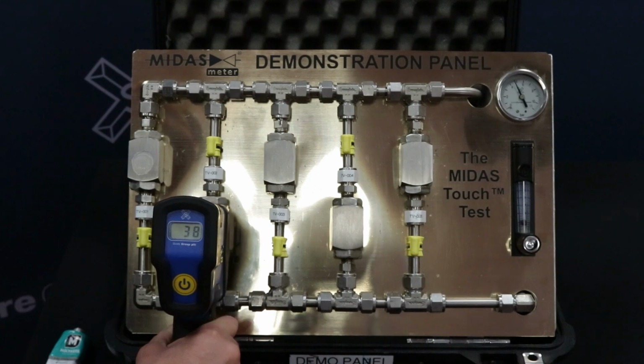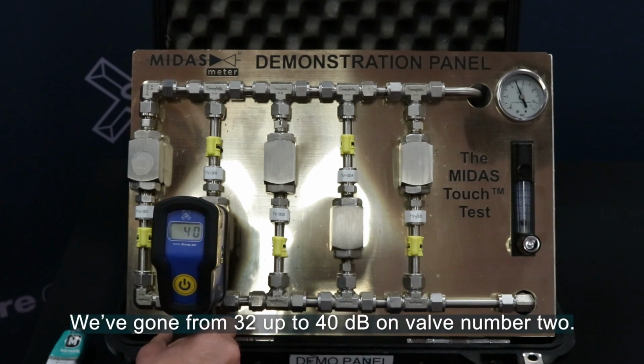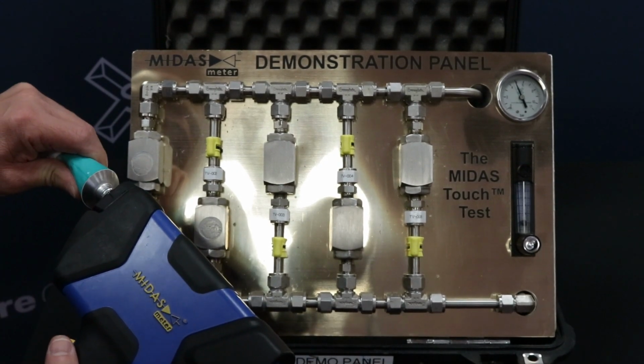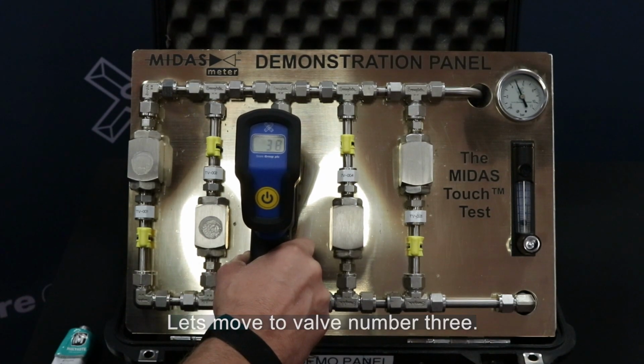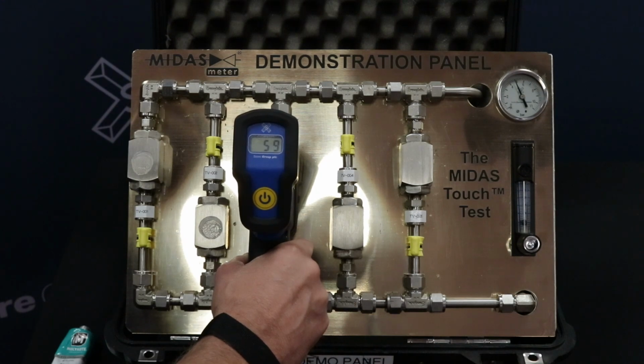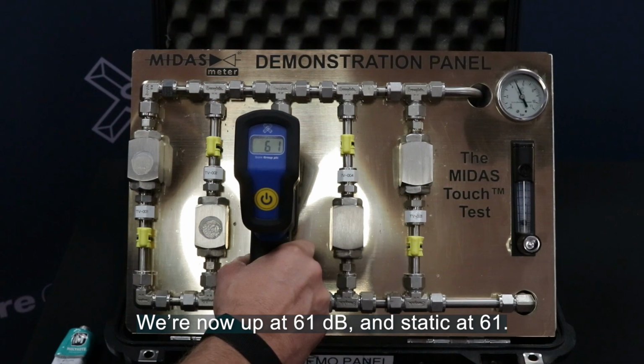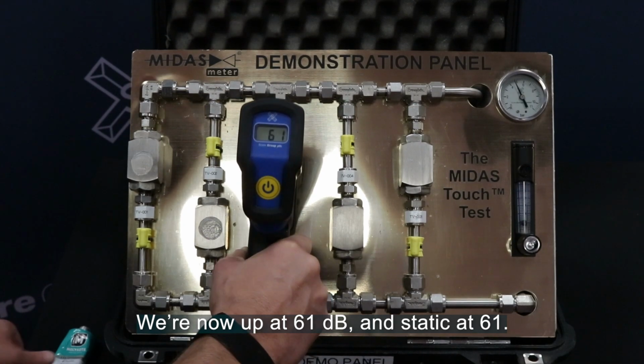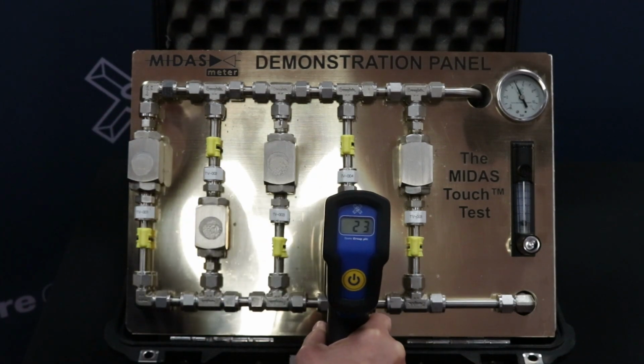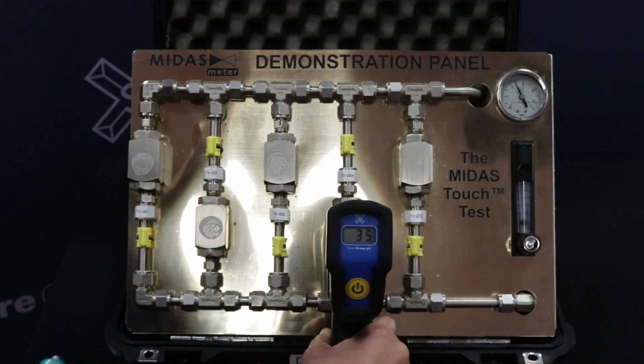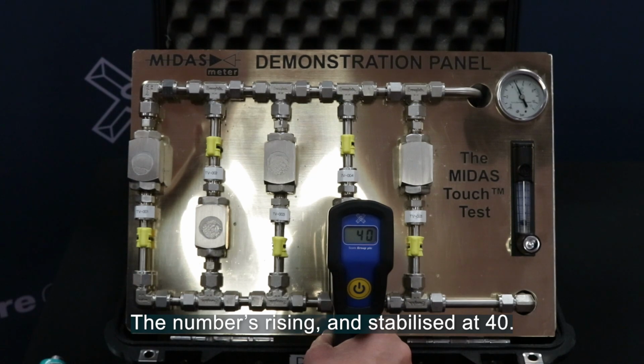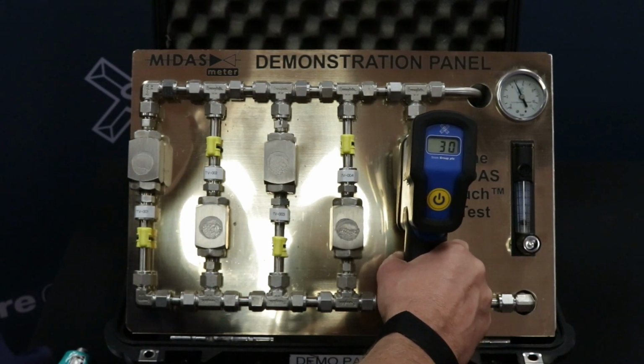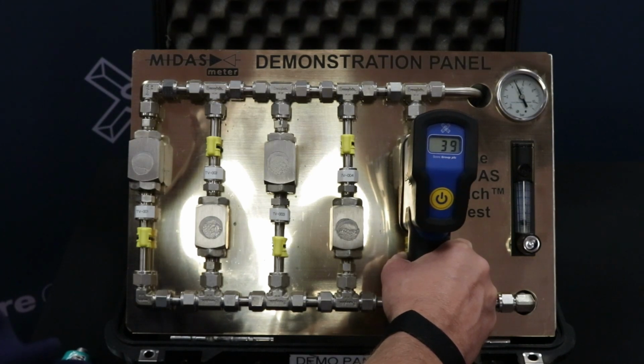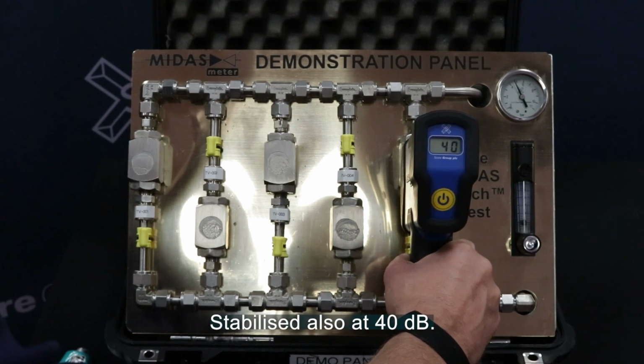Give that a few seconds to stabilize. We've gone from 32 up to 40 decibels on valve number 2. Let's move to valve number 3. We're now up at 61 decibels and static at 61. Move to valve number 4. Numbers rising and stabilized at 40. And finally, the 5th valve, body reading. Stabilized also at 40 decibels.